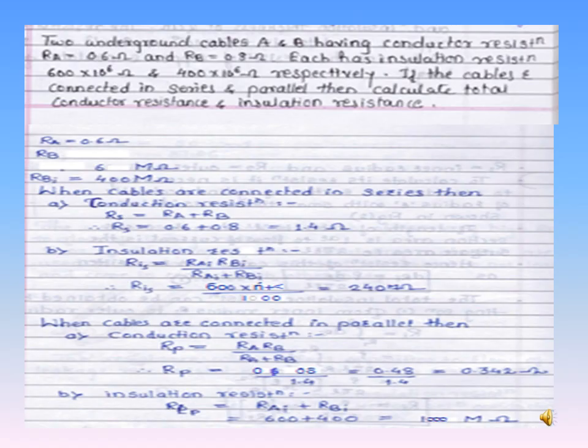This slide shows a typical example on underground cables. Cable A has conductor resistance RA = 0.6 Ω and insulation resistance = 600 MΩ. Cable B has conductor resistance RB = 0.8 Ω and insulation resistance = 400 MΩ. We are asked: if these cables are connected in series and in parallel, what are the resultant conductor resistance and insulation resistance? An important point: when cables are connected in series, their conductor resistances are in series but their insulation resistances appear in parallel.